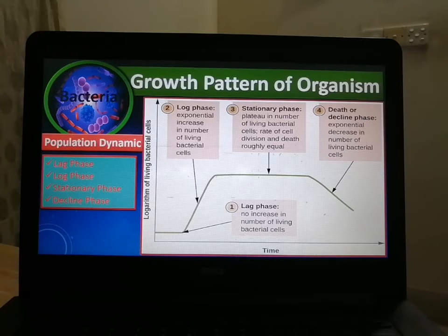For any system, if we allow the bacteria to come up here, meaning the lag time and the log time have passed and the bacteria reach that level of number, and then we try to control it here, the system will always be dirty. The system will always be under fouling, the heat exchanger will always be under fouling, and the biocide requirement will always be very high, and the biocide dose will be insufficient. If we count bacteria, we'll get 10^7, 10^8, 10^10. We can't control it at that level. We can't control bacteria down to the required 10^4 or 10^3 level as our expectation.